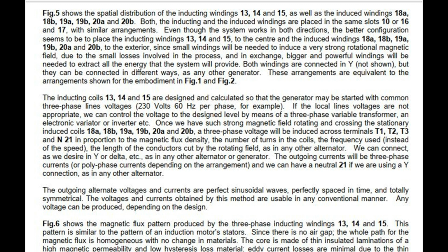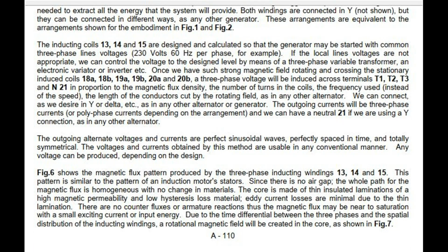Fig 6 shows the magnetic flux pattern produced by the three-phase inducting windings 13, 14 and 15. This pattern is similar to the pattern of an induction motor's stators. Since there is no air gap, the whole path for the magnetic flux is homogeneous with no change in materials. The core is made of thin insulated laminations of a high magnetic permeability and low hysteresis loss material. Eddy current losses are minimal due to the thin lamination. There are no counter fluxes or armature reactions, thus the magnetic flux may be near to saturation with a small exciting current or input energy.